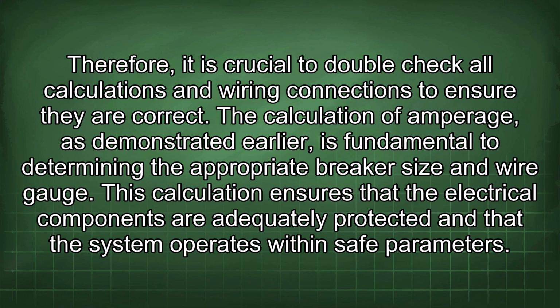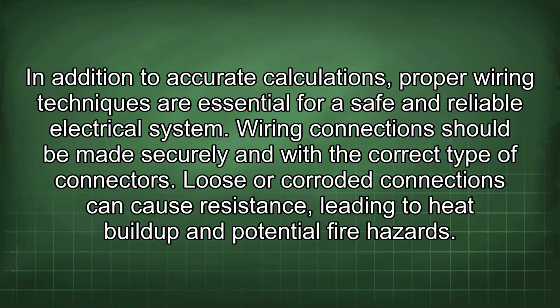The calculation of amperage, as demonstrated earlier, is fundamental to determining the appropriate breaker size and wire gauge. This calculation ensures that the electrical components are adequately protected and that the system operates within safe parameters. In addition to accurate calculations, proper wiring techniques are essential for a safe and reliable electrical system. Wiring connections should be made securely and with the correct type of connectors.